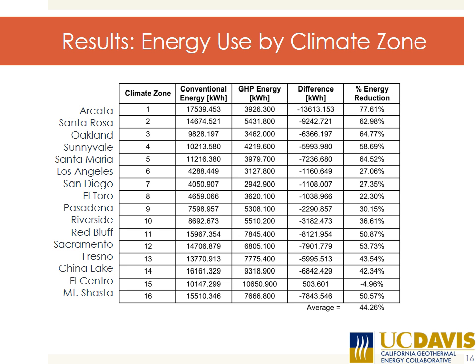There are several things. One, if you look at the coefficient of performance, the COP numbers for geothermal heat pump systems, for a number of years they were around 3 or 4. What that COP is, is the ratio of the amount of heat energy made available versus the amount of energy consumed. So a COP of 3 would mean that 3 times the amount of energy is provided to the room or building than was consumed in getting that heat energy there. The COPs are now approaching numbers on the order of 5 and 6.